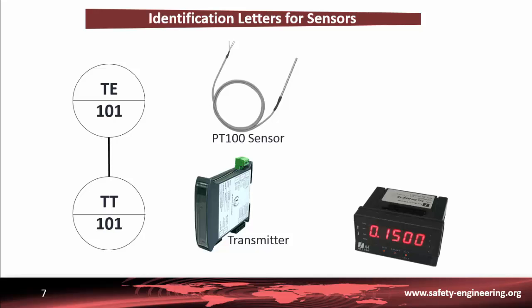Indicators may be as simple as a pressure gauge or more complex such as a digital readout device. The symbol associated with an indicator is the letter I. For example, PI means a pressure indicator not connected to a controller. FIT means a flow indicator with a transmitter — this kind of sensor could be connected to a controller.